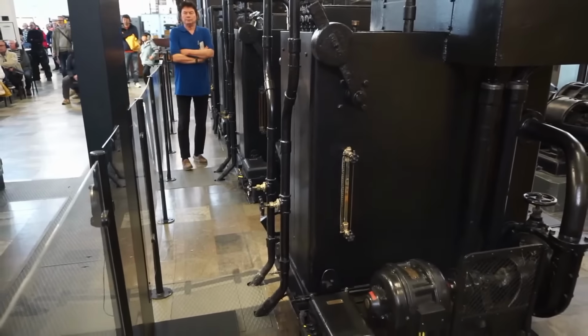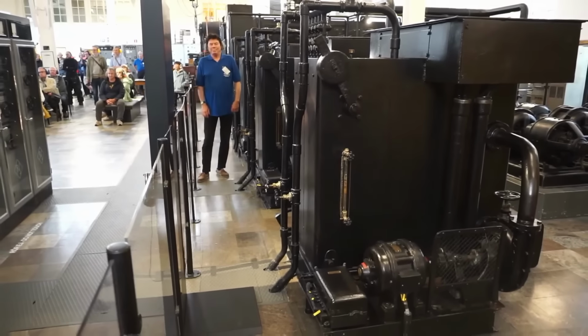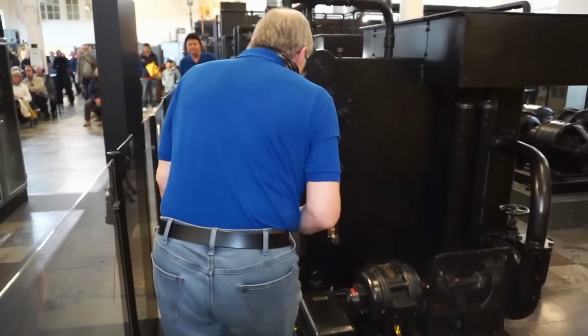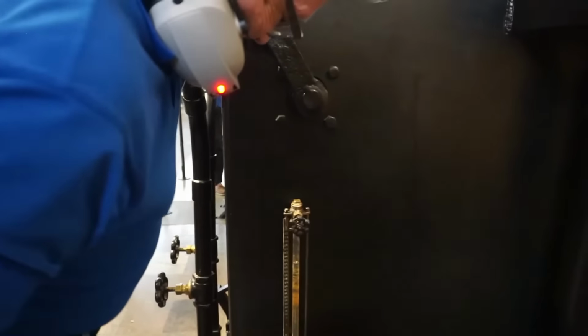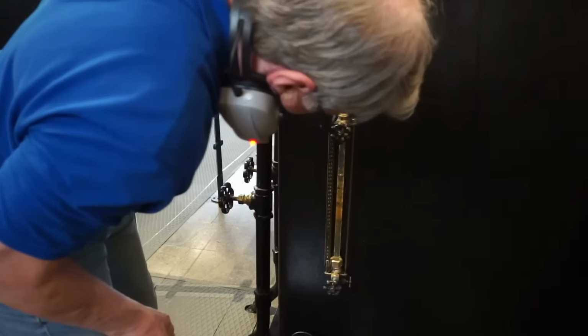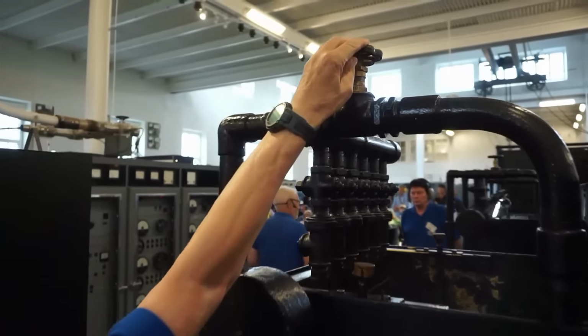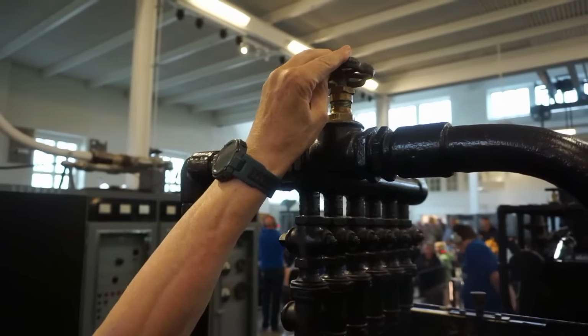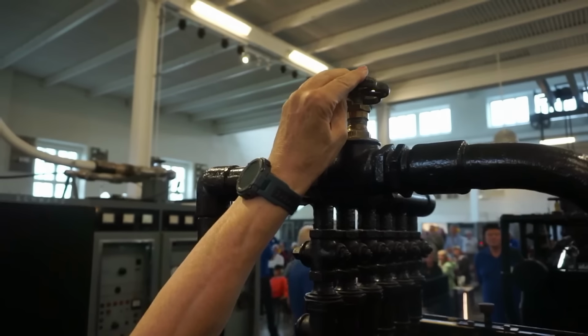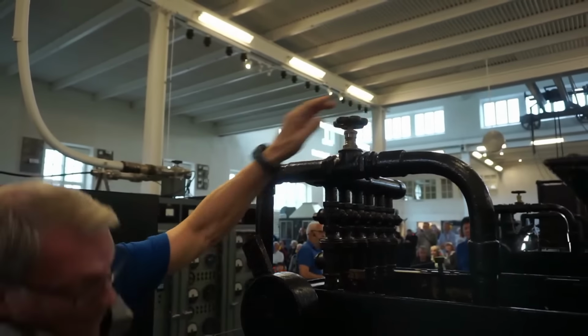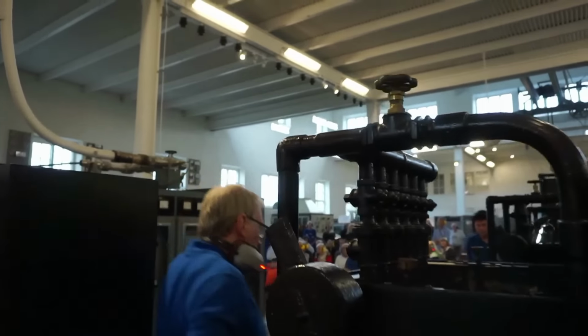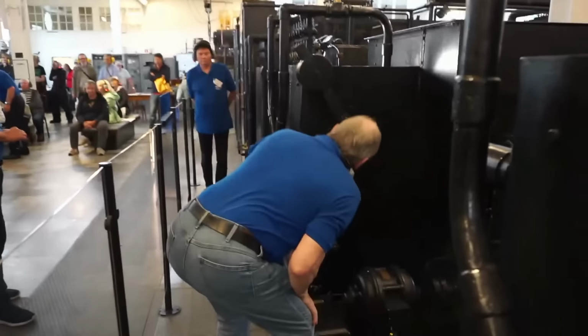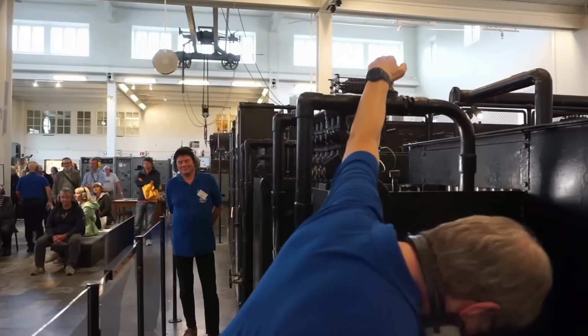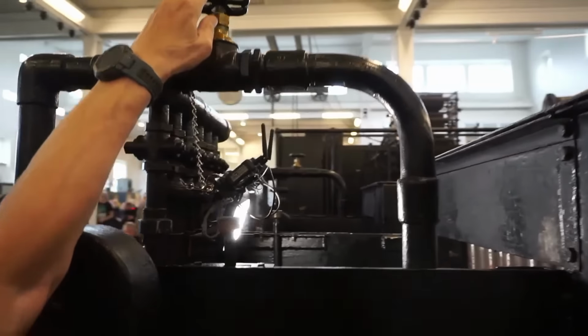Jan-Åke will control the liquid levels in the rheostats, because the liquid gets hot and evaporates, so sometimes we have to add some water. Here are 3 rheostats. One is a backup. They are used to control the motor speed. This is a start resistor, and it will hold down the initial power to the motor. Later on it is used to fine-tune the motor speed. It is connected to the rotor on the main motor via slip rings and cables.